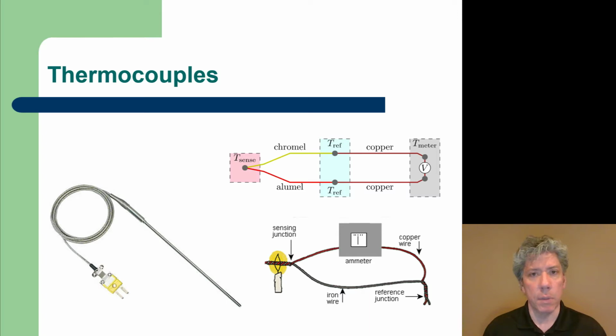On the left you'll see a typical industrial thermocouple. You notice that the place where it plugs in is that yellow plastic housing. One interesting thing about these, they typically have the same type of material for the blades that the wire is made from. So if this is what's known as a type K thermocouple, that's a chromel alumel wire set, then the blades there will be made out of the same materials. Now you'll notice, I don't know if you can tell from the picture, but typically one blade will be a little bit wider than the other, and the reason for that is so you can't plug it in backwards.